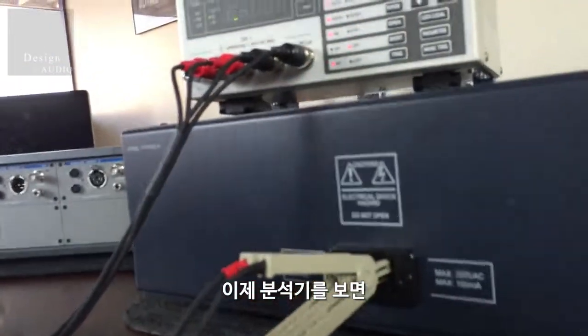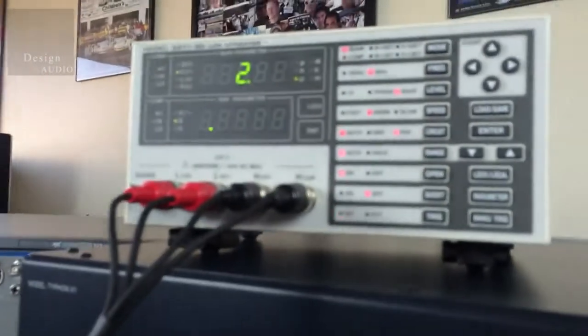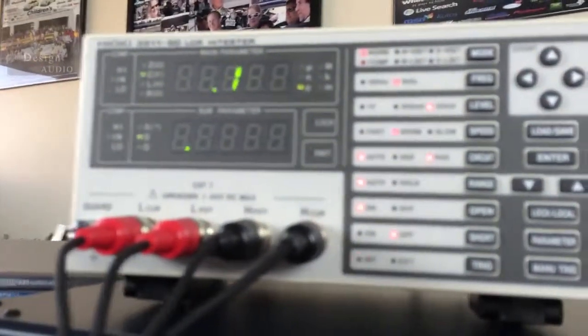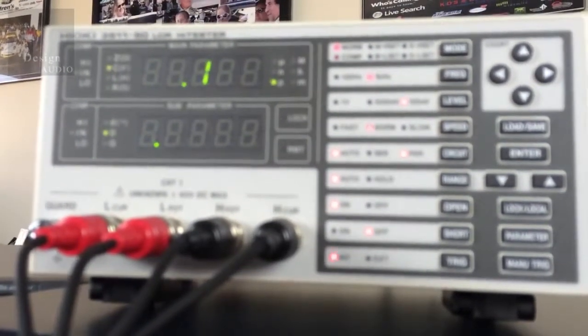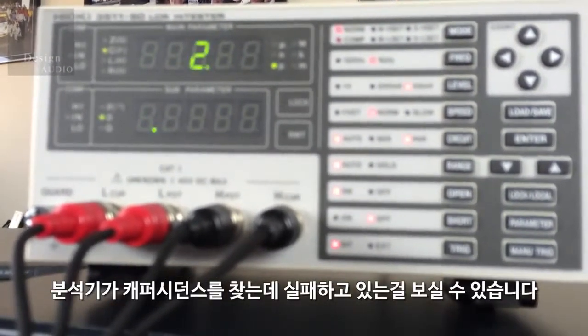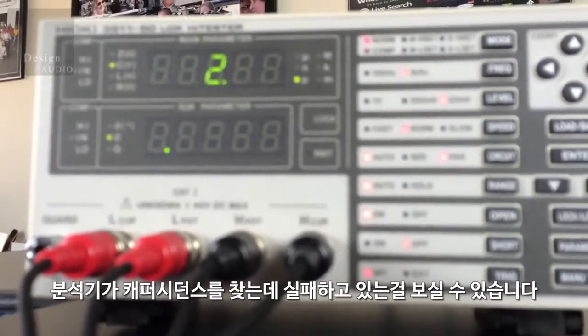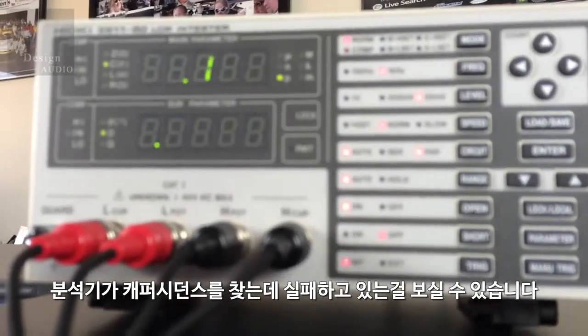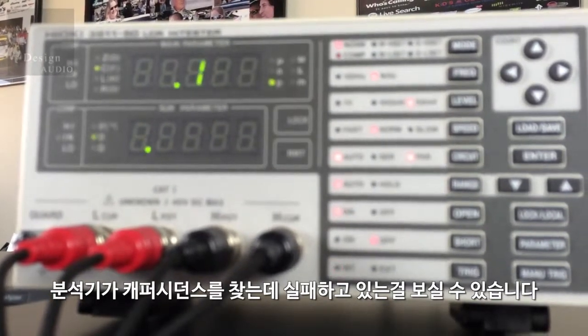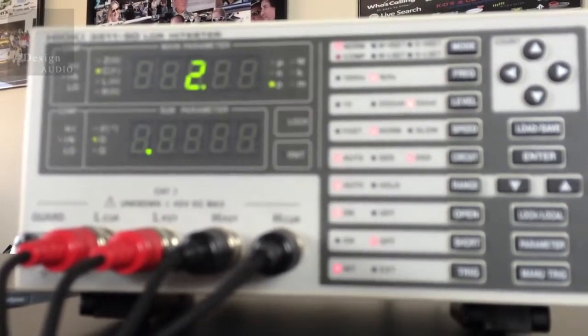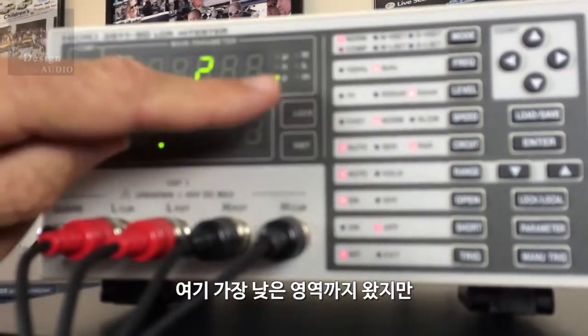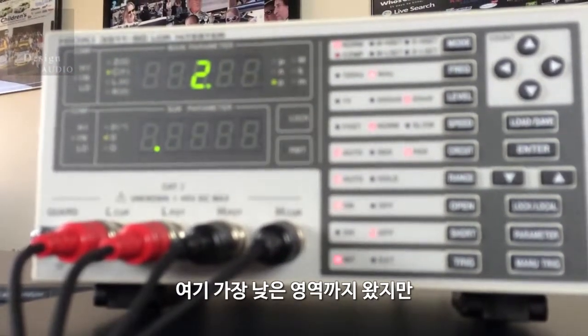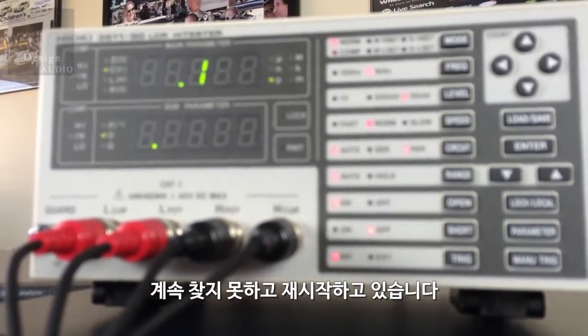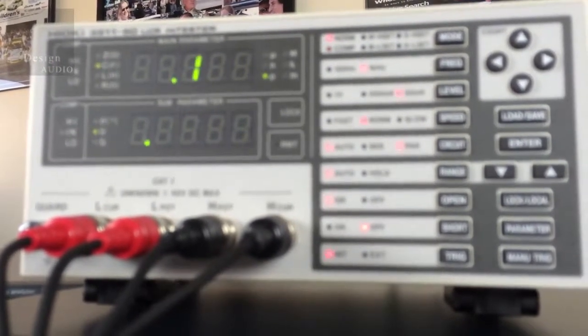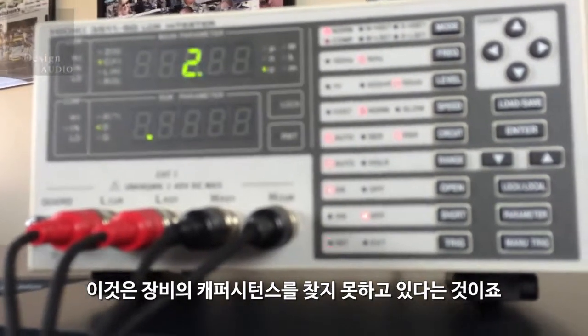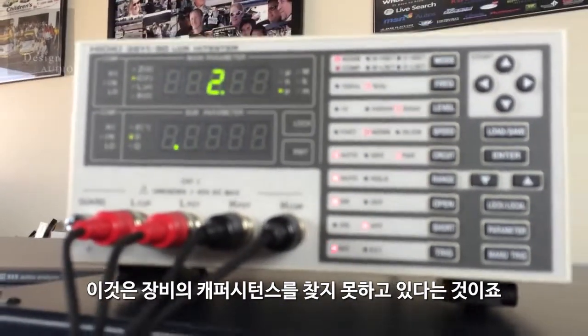Now if you look at the display, you can see that the analyzer's searching. It's trying to find a capacitance reading, and it's having trouble doing that. So right now it's looking down in the picofarad range, which is very low. And as you can see, it keeps searching, gets confused, and starts all over. This indicates that it can't find any capacitive reactance of the unit.